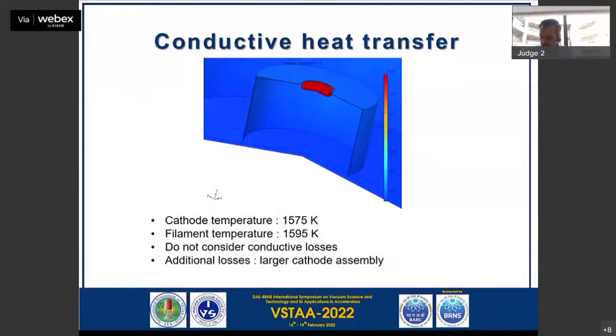Since the filament temperature reduces, filament fusing will not happen, so the life of the cathode assembly will increase. The filament temperature now needs to be most optimal. Previously it was rising to 3500 Kelvin, very close to the melting point of tungsten. Once the temperature rises further, the life will go down.